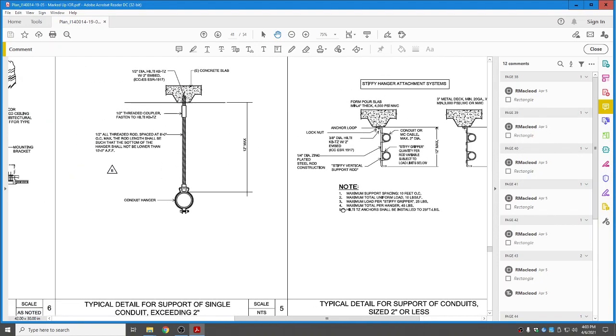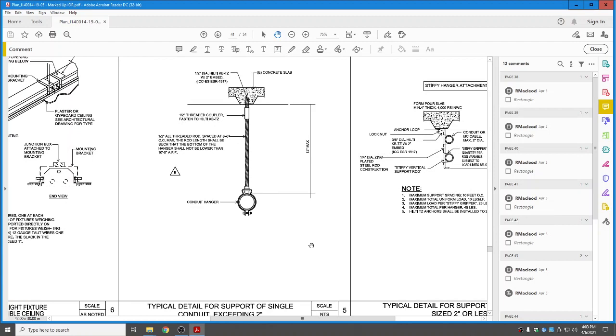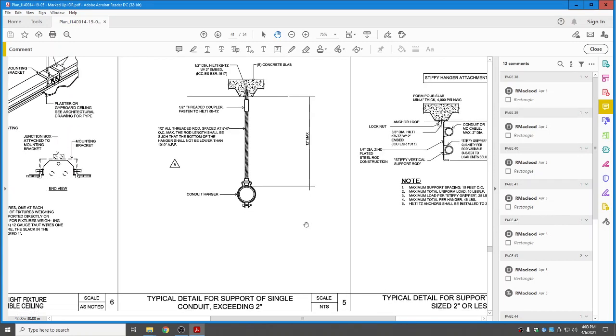Now let's jump over to the typical detail for conduits exceeding 2 inches. And you note that this also has a 12-inch maximum. So in a structural steel building where you've got to run your conduits, sometimes you're going to run into some beams that are 2 feet or 3 feet deep on the girders.